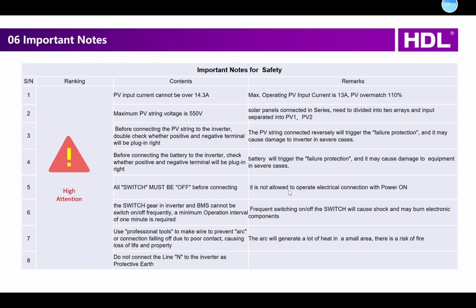And the maximum PV string voltage is 550 voltage. In this case, you need to pay attention to the quantity of solar panels you connect to one MPPT port, because the most common standard solar panels have a voltage of around 40 volts DC, and in this case we can connect a maximum of about 13 pieces for each MPPT, and this is enough because the inverter rated power is like 5,000 watt.